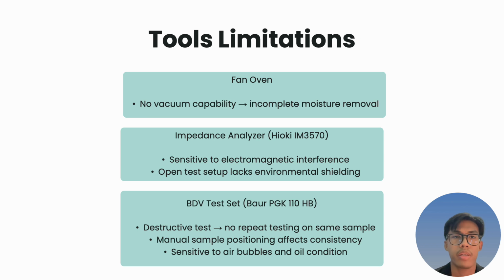From the experiment, the fan oven lacks a vacuum function, which reduces impregnation efficiency and may leave residual moisture, while the impedance analyzer is sensitive to environmental interference and does not fully isolate external noise at low frequency, while BDV test is a destructive method, preventing repeatability on the same sample and also affected by sample positioning, oil condition, and the presence of air bubbles. Despite the challenges, each tool provided critical data for assessing the insulation behavior.